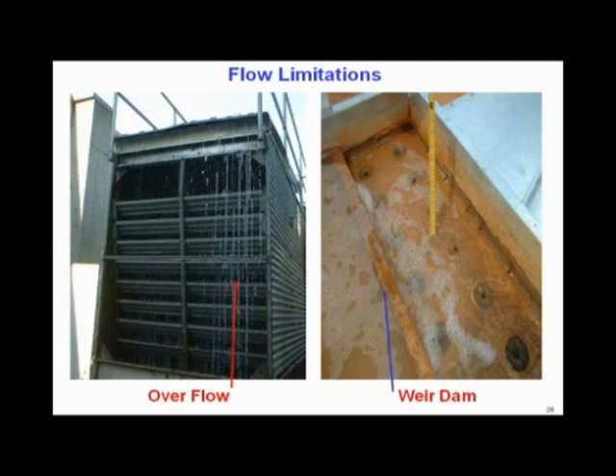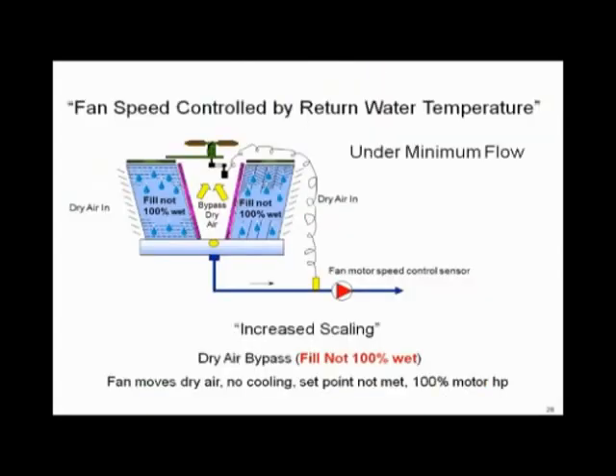The weir dam ensures the face of the tower always has some water on it — there's never a dry passageway where air can bypass the fill. We want that air to always have to pass through some moisture on the face of the fill to keep the tower working. The weir dam lets you turn down to 50% easily.